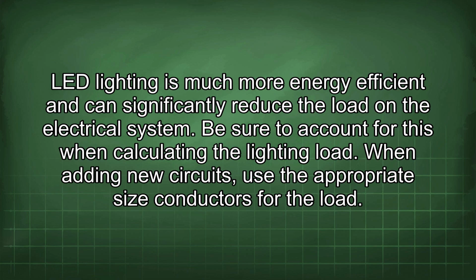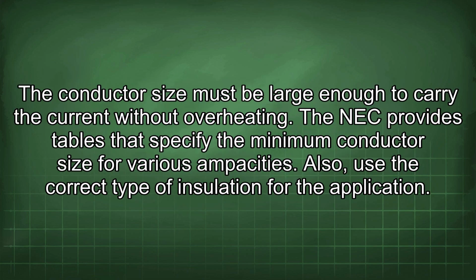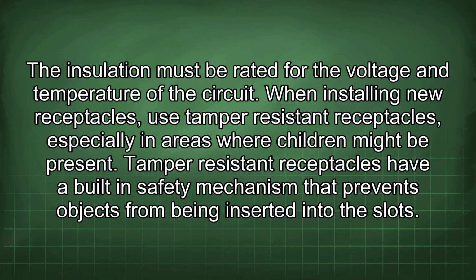When adding new circuits, use the appropriate size conductors for the load. The conductor size must be large enough to carry the current without overheating. The NEC provides tables that specify the minimum conductor size for various ampacities. Also, use the correct type of insulation for the application. The insulation must be rated for the voltage and temperature of the circuit.